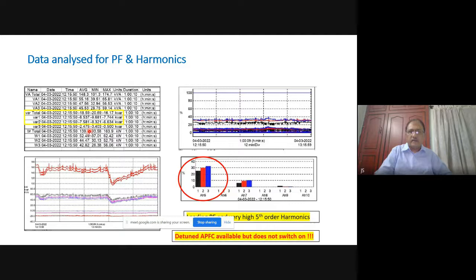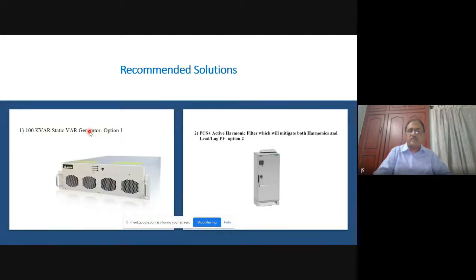Actually, a detuned APFC is already available, but what we recommended was an SVG, static var generator. That is option 1. This client is in a rented place, so he suggested I will take a static var generator, take care of my leading power factor. But in the near future, with the TNERC coming back once again with the revised harmonic limits and penalty in Tamil Nadu, they may have to go for an active harmonic filter.